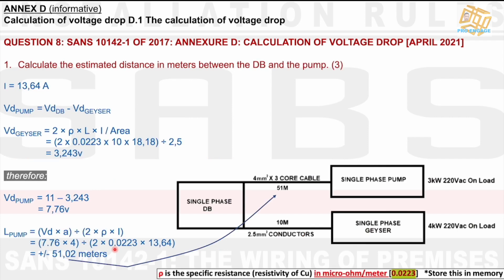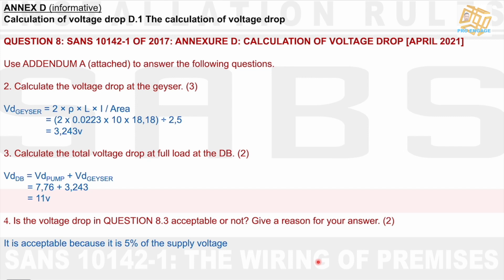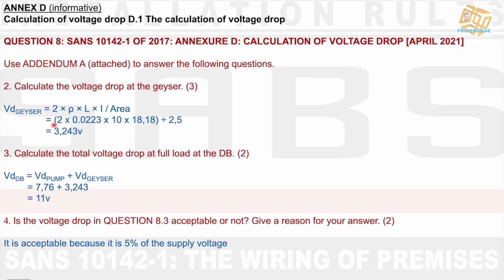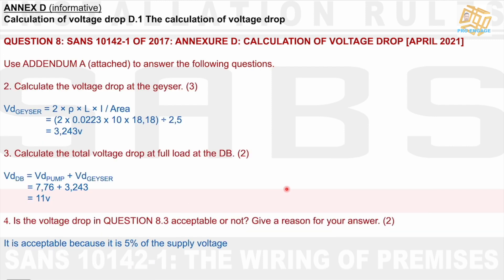That 51 meters is the estimated distance between the DB and the pump. You can substitute it back into the formula to verify the voltage drop. Moving to question 8.2, which uses Addendum A (the attached table): calculate the voltage drop at the geyser. We've already calculated this as part of 8.1. It equals 3.24 V — essentially we were killing two birds with one stone.